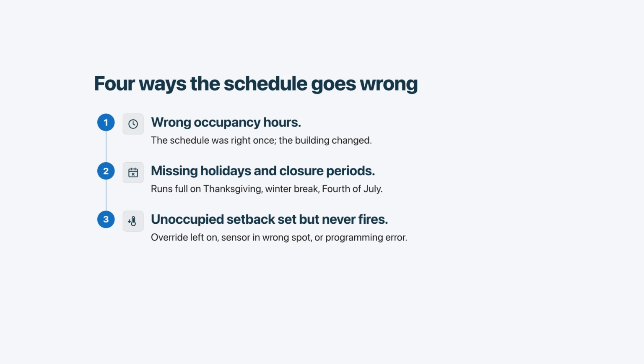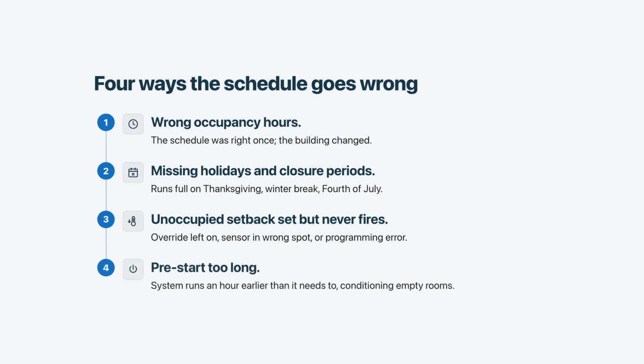Number 4 is a pre-start overshoot. The system is programmed to reach comfortable temperatures by 9 a.m., so the controller starts cooling maybe at 6 a.m. to give itself margin. In many buildings, that pre-start might only need to be 45 minutes, not 3 hours. Those 2 extra hours are pure waste. All 4 of these are configuration problems, not equipment problems. You're not changing the equipment here. They all get fixed at the controller, not in the mechanical room.